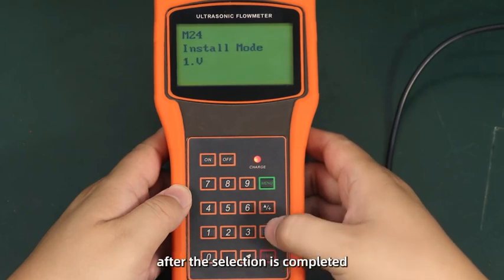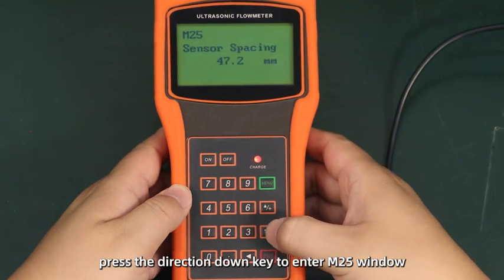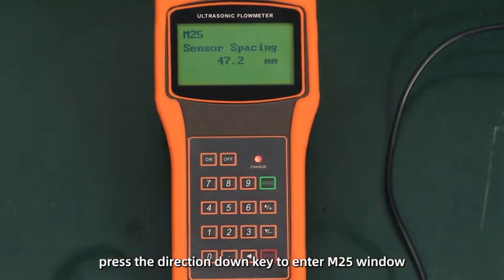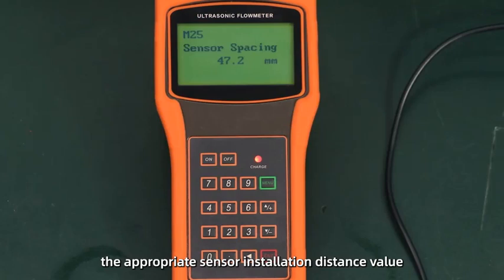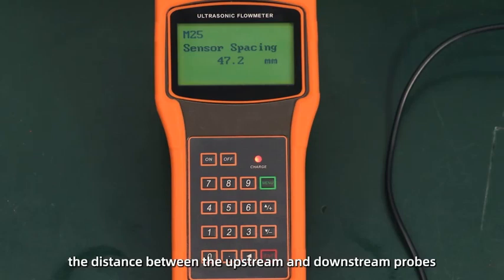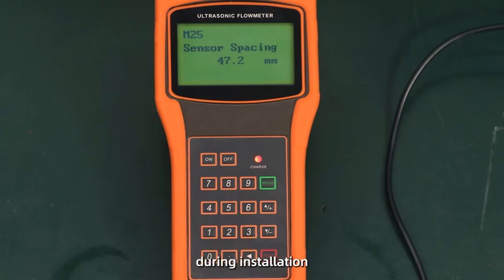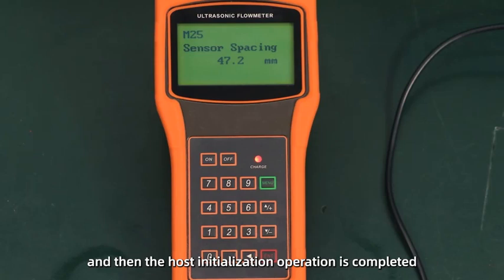Press the direction down key to enter M25 window, and the host will convert the appropriate sensor installation distance value according to the input parameters, which is the distance between the upstream and downstream probes during installation, and then the host initialization operation is completed.